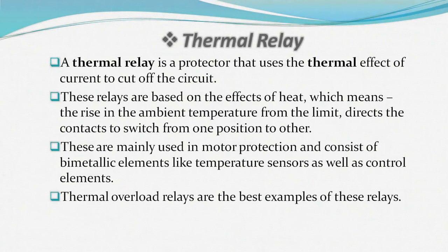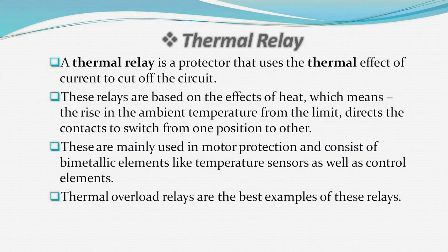Thermal relays are protectors that use the thermal effect of current to cut off the circuit. These relays are based on the effects of heat — the rise in ambient temperature beyond a limit directs the contacts to switch from one position to another. They are mainly used in motor protection and consist of bimetallic elements like temperature sensors as well as control elements.